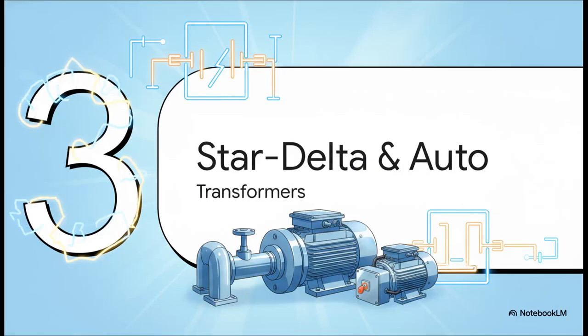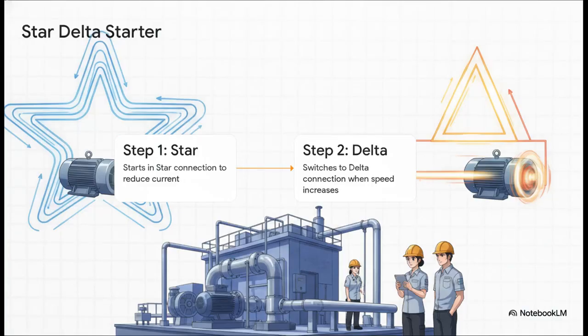That brings us to Section 3, Star Delta and Auto Transformers. Since DOL only cuts it for the small stuff, what about the heavy-duty industrial water pumps? That's where Star Delta starters come in. And the way they work is actually pretty brilliant. Step 1, the starter fires up the motor in a star connection. This clever little trick drastically reduces that massive starting current we talked about earlier. Then, for step 2, once the motor builds up enough speed, the starter automatically switches it over to a delta connection to run at full power.